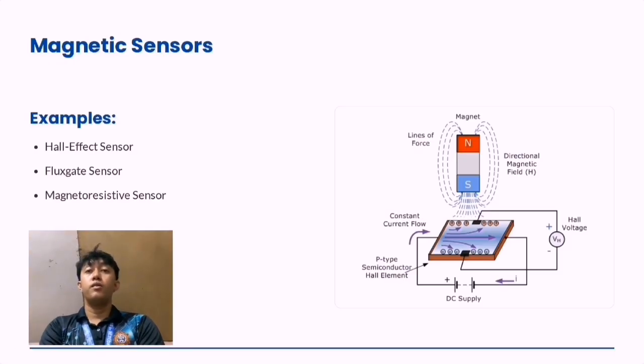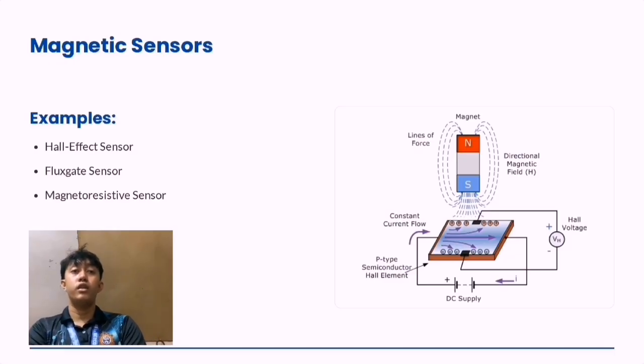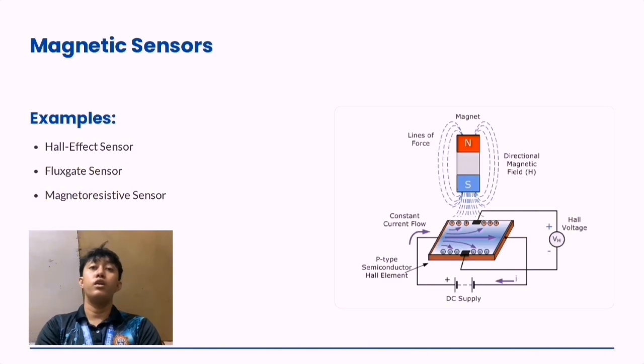The second example is the flux gate sensor. A flux gate sensor typically has ring cores of a highly magnetically permeable alloy around which are wrapped two coil windings, the drive winding and the sense winding. Some sensors will also have a third feedback winding if the sensor is to operate in closed loop.